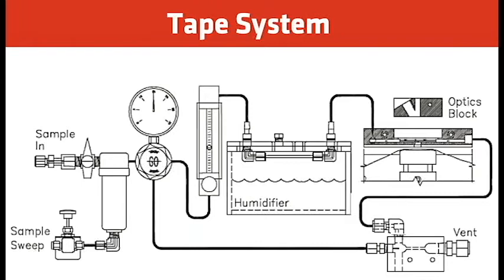The eductor's basic design is to maintain atmospheric pressure out of the sample chamber and vent to atmosphere or to flare. The eductor requires a drive gas — we come off our regulator at 15 psi, driving the eductor with 15 psi, basically creating a venturi that sucks in air from the bottom, maintaining atmospheric pressure, and goes out the vent. The vent rate is typically 1000 cc's per minute plus the 80 to 100 cc of sample going through the sample chamber.